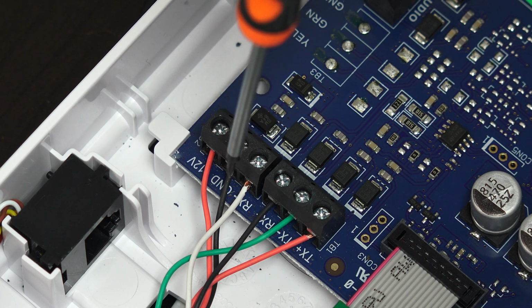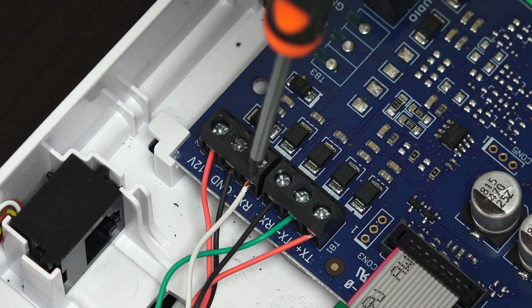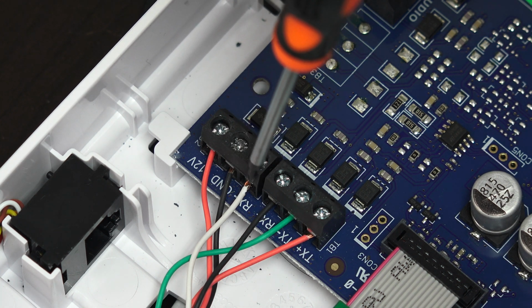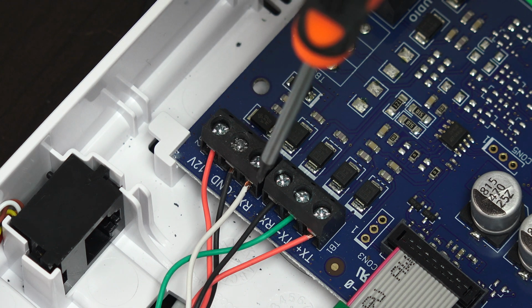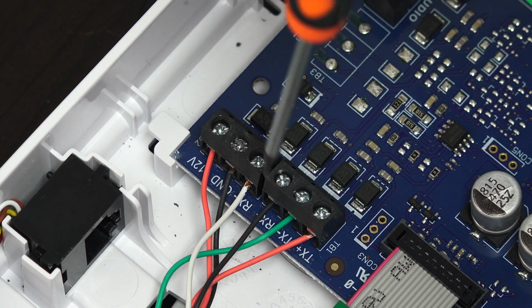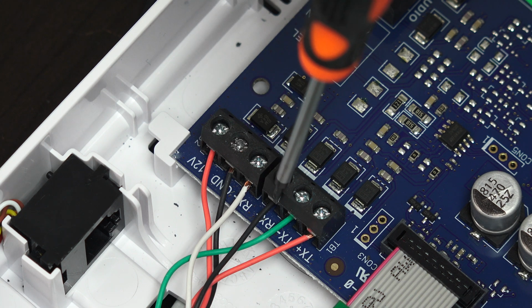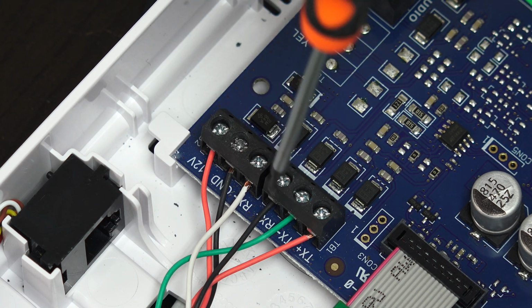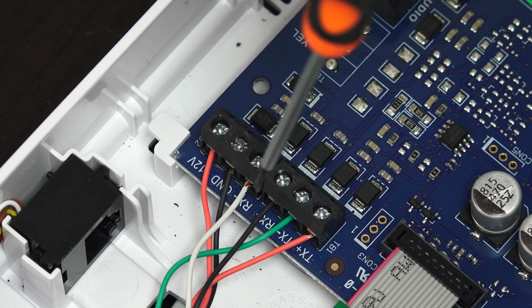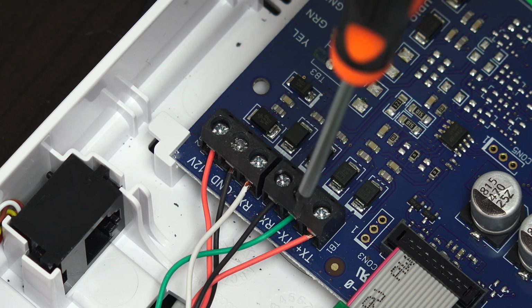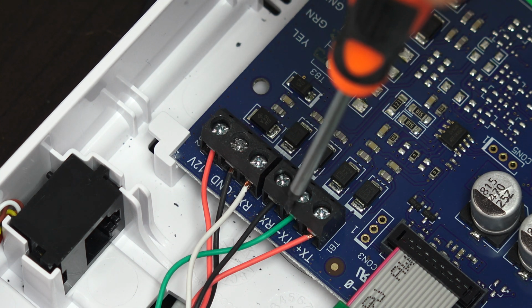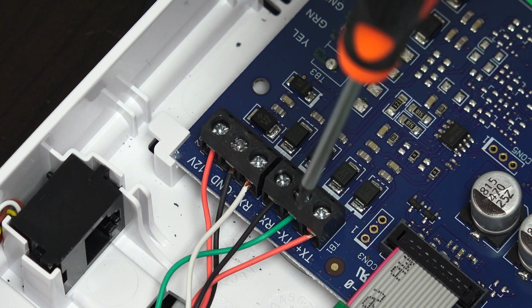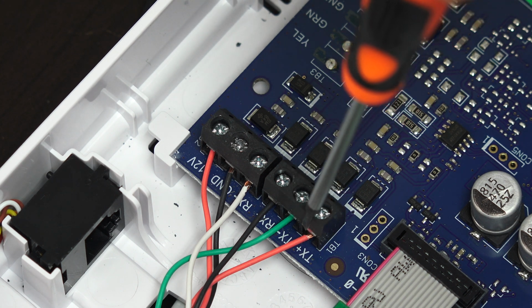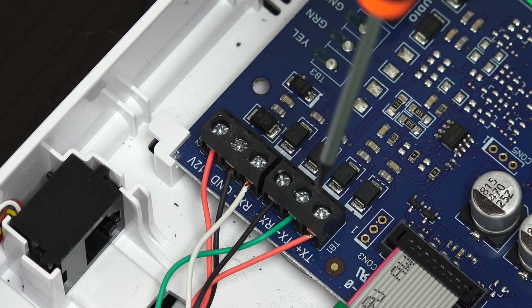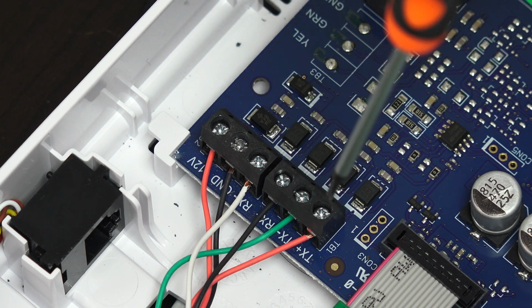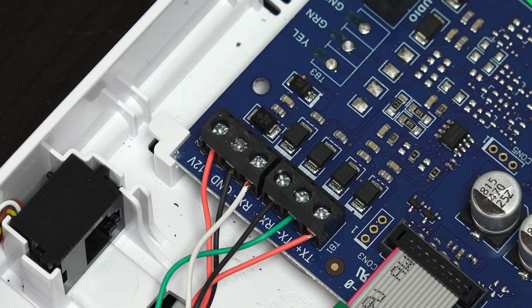But first we have the RX minus connection. So we have the white cable, and that's going to the TX minus at the PCL422. Then we have the RX plus, which is going to the TX plus on the PCL422. In this case, we use the black wire. Then we have the TX minus, which we use the green wire in this case. So that's going to go to the RX minus on the PCL422. And lastly, we have the TX plus. In this case, we use the red wire. And that's going to go to the RX plus on the PCL422.